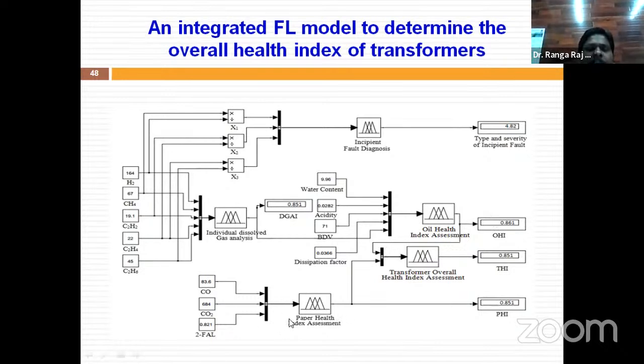Next important part is paper. We know that in DGA test we can observe two gases, CO and CO2, which give information about the paper condition. We also have the furan analysis test. Furans are released into the oil once the sample ages and the paper loses its thermal properties, releasing furan contents like 2-FAL and 3-FAL. We perform this furan test on the oil, but the information obtained relates to the paper.